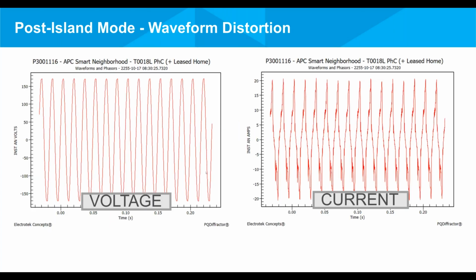Now, furthermore, I talked about harmonic introduction into the power quality signature. Here's an example. With the microgrid being an inverter-based system, the inverter introduces harmonics into the system as opposed to power from the grid. This depicts the voltage signature. You might not see the harmonics clearly on the voltage, but on the current, you can see them clearly, at the peaks and the valleys. This is just to depict the waveform distortion during the islanding situation.